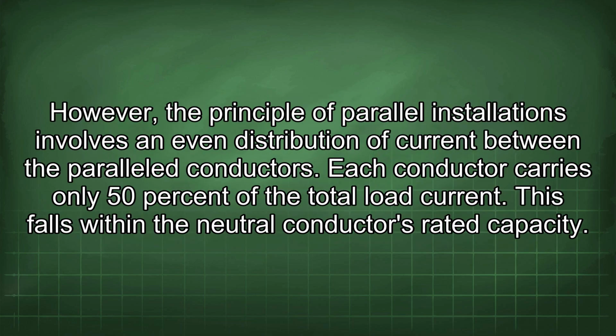However, the principle of parallel installations involves an even distribution of current between the parallel conductors. Each conductor carries only 50% of the total load current. This falls within the neutral conductor's rated capacity.